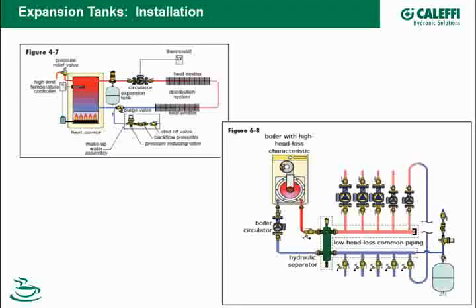But by doing it this way, all of the pumps in the system are pumping away from the point of no pressure change. All of the head pressures are additive. The system will perform better.